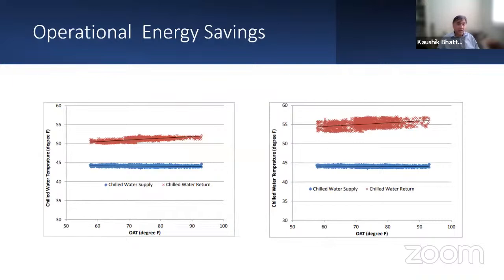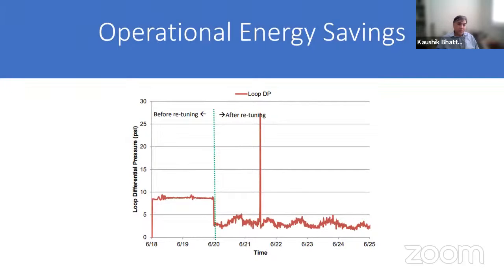These are other problems, such as delta T for chillers. Normally, for good performance of a chilled water or cooling water system, you need to operate the chiller at a high delta T. In many cases, you find that these chillers do not maintain a good delta T, which affects the performance of the chilled water system adversely. This is really getting into detail, but I just touched upon the slide here. This is adjusting the loop differential pressure for a pump. You can see that after performing the recommissioning, the pressure set point of the pump was reduced, and obviously your pumping energy is a function of head and flow. So when you reduce the head, you reduce the energy.